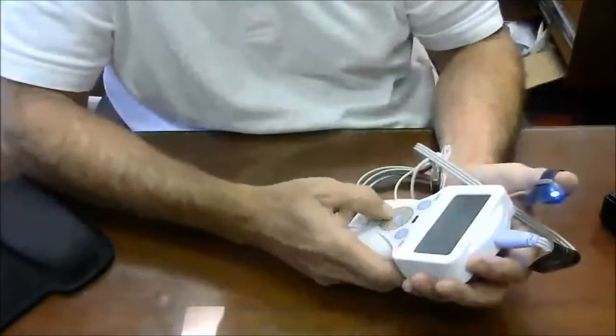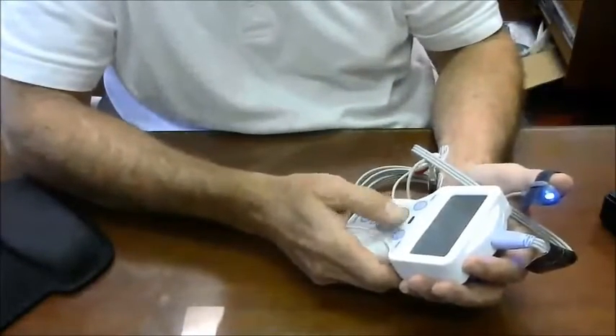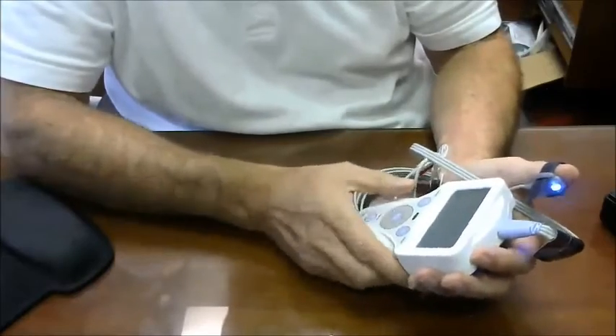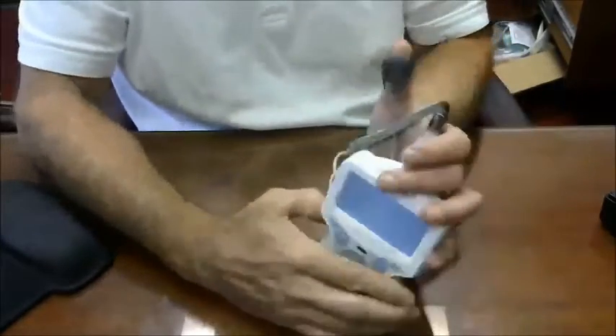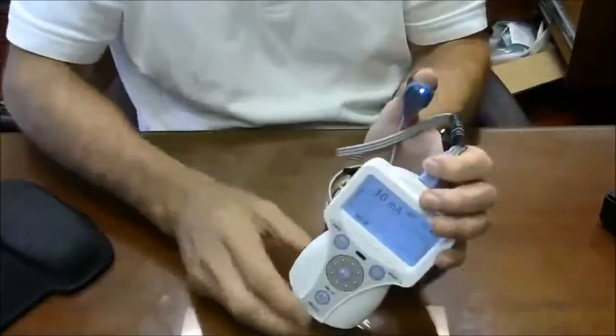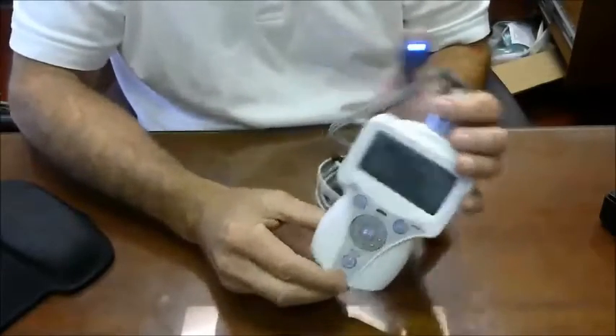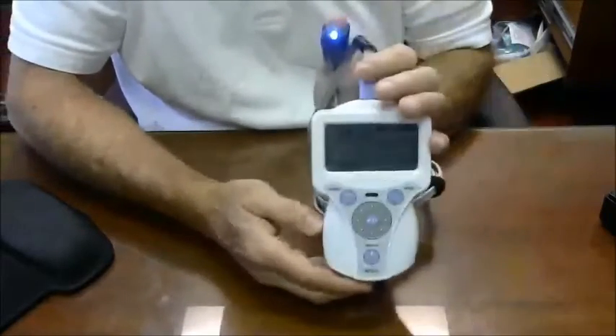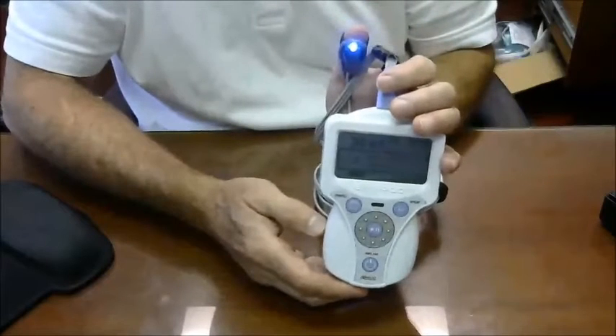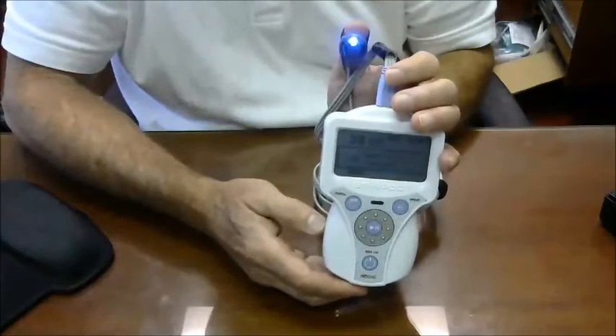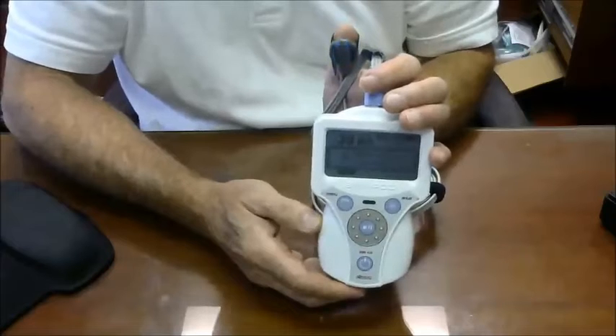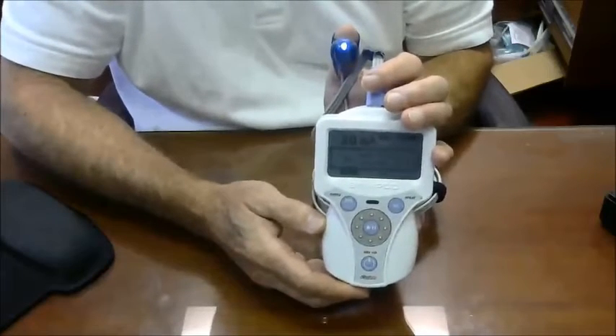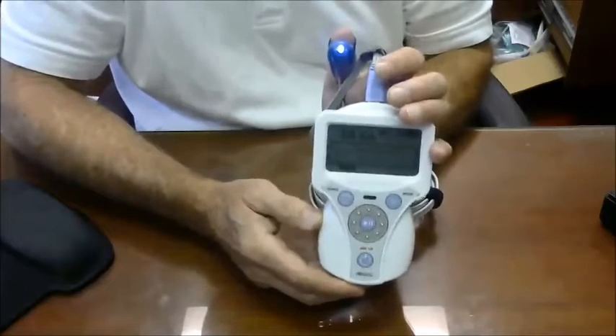So as I show this again, I'm going to go back up to 30 milliamps, press enter. Just to show you a few things, if I lose an electrode, like when an electrode doesn't come on, the monitor will say open circuit detected. Now, we got a lot of open circuit detected before when we had a bad cable. So if you had a cable in and they had it securely connected to 2 electrodes and you got this message, it meant your cable was bad.